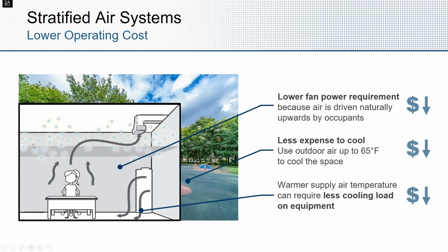In terms of operating cost, there is a deduct associated with fan horsepower, because you're supplying air at low velocity into the space. Usually 0.05 inches or less is the typical pressure drop across these diffusers, or what's needed to move the air through the diffusers themselves. Less expensive to cool, so now we're dealing with 65-degree air on average instead of 55 degrees.